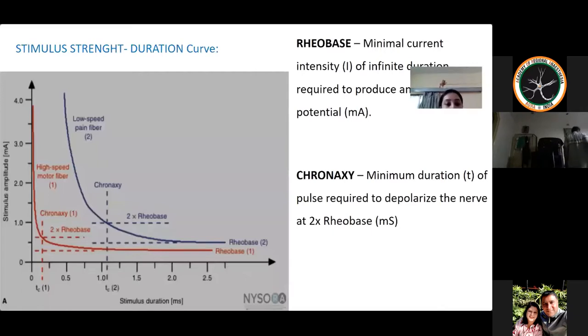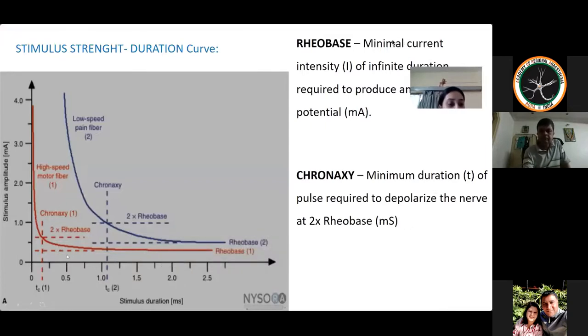Now, this constant current is produced by the PNS by raising or lowering the voltage in response to the change in resistance. This relationship is explained by the stimulus strength duration curve. That is, in the picture, you can see the red line is for the motor fiber, and this is for the pain fiber. Now, rheobase is defined as the minimal current intensity of infinite duration required to produce an action potential, and a current below rheobase will not generate any motor response or depolarize the nerve.